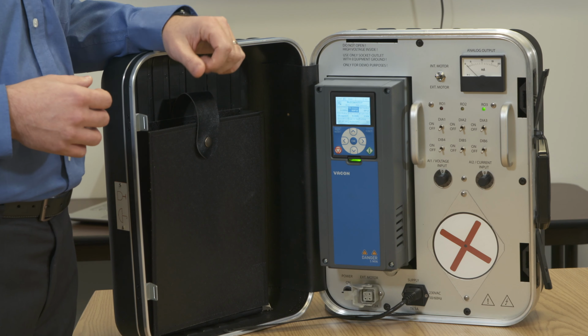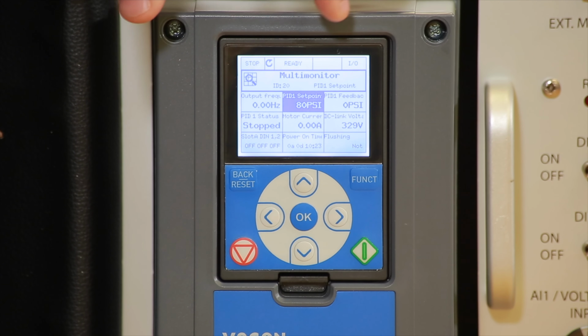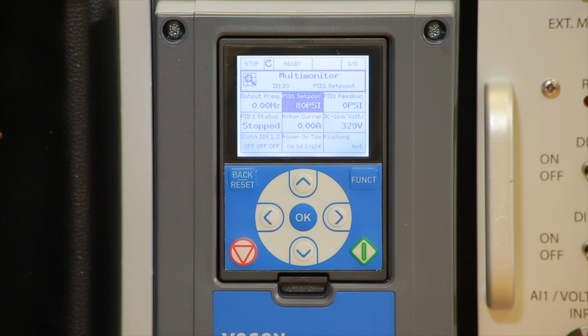DC link voltage, this is a very important feature to have and display constantly on the keypad because we want to know what the line voltage is. So DC link voltage is fantastic. This is slot A digital input 1, 2, and 3. We have off, off, and off. These are the first 3 digital inputs that are being monitored. So whenever 1 is on, if we have a selector switch, a hand-off-auto, we can utilize digital input 1, 2, 3. And the drive will tell us which one is on and off. Fantastic for troubleshooting, letting you know that your selector switches are actually working or not. And as we do the start command with digital input 1, we'll see the status change from off to on. And it's very great for troubleshooting at any time.